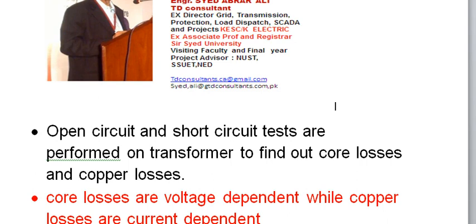The winding losses are called copper losses even if the winding is made of aluminium. The generic name may also be 'load losses' — losses that occur on load. So 'copper losses' does not indicate that the winding must be made of copper; it may be aluminium as well.